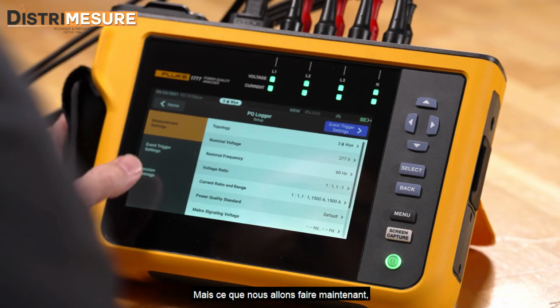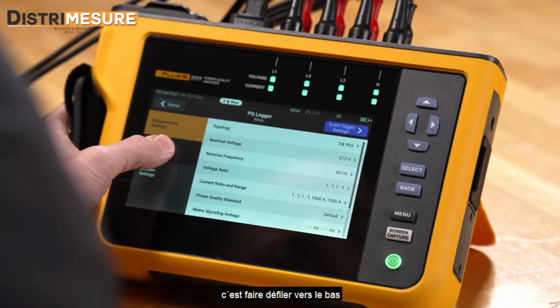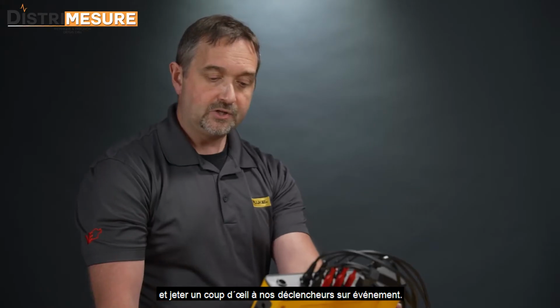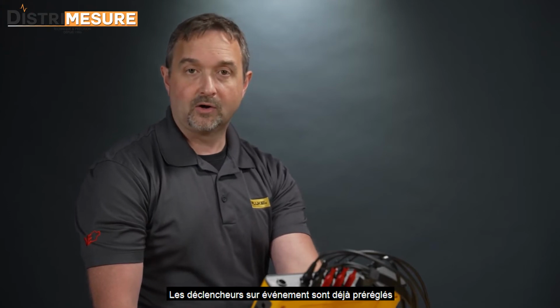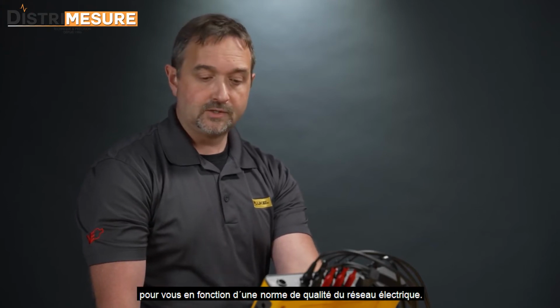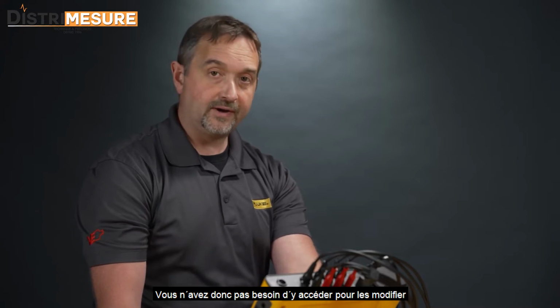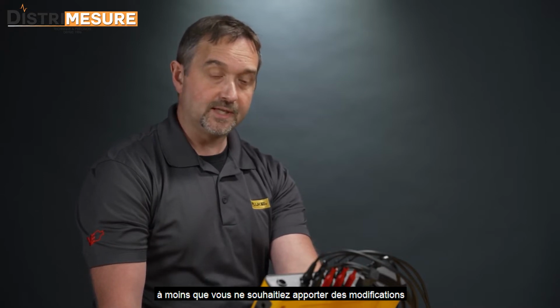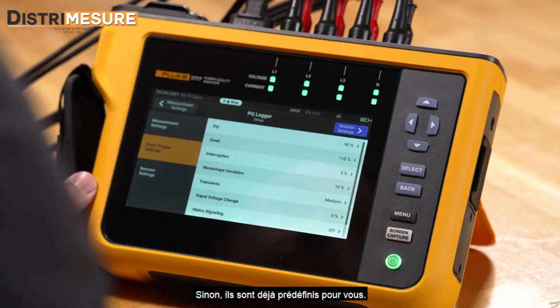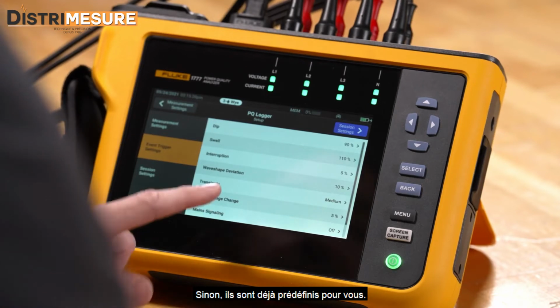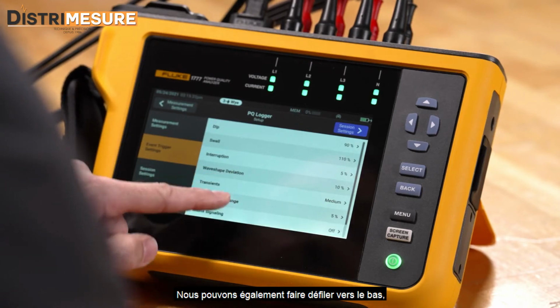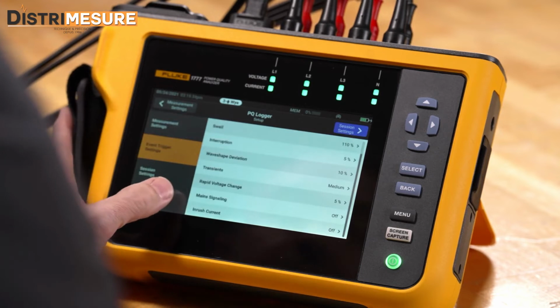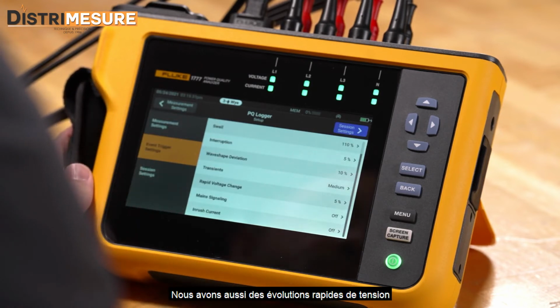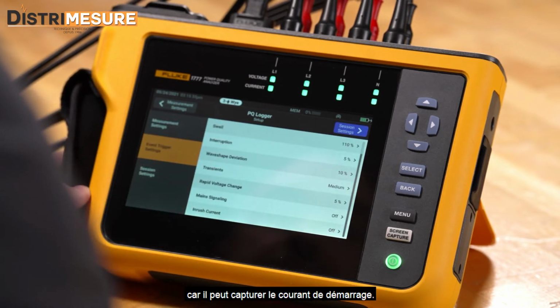But what we're going to do here is go down and take a look at our event triggers. Event triggers are already preset based on a power quality standard for you, so you don't actually need to modify these unless you want to make changes from a standard. We also have the ability to scroll down. We can make modifications to the transient triggering. We have rapid voltage changes as well as inrush capture.